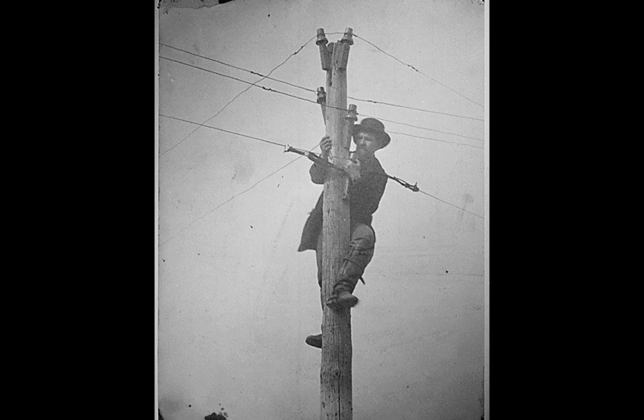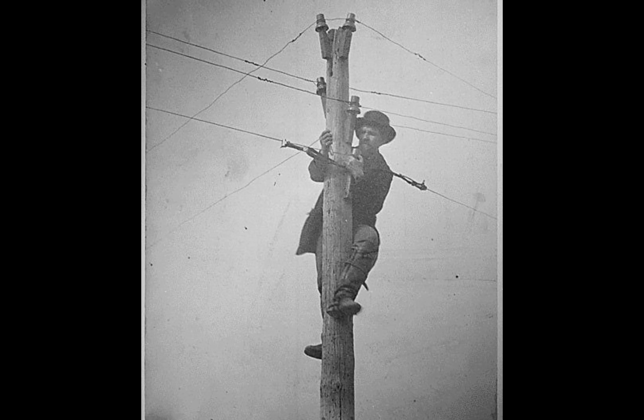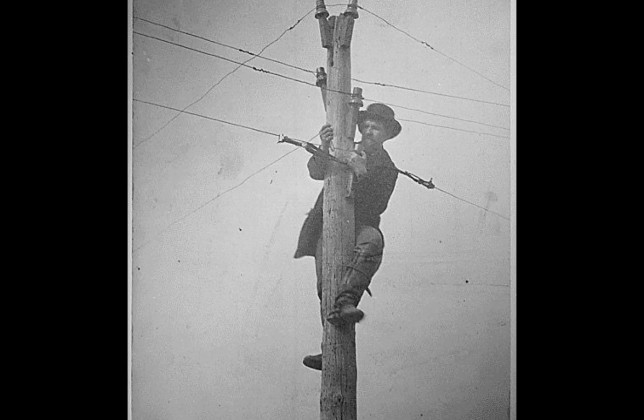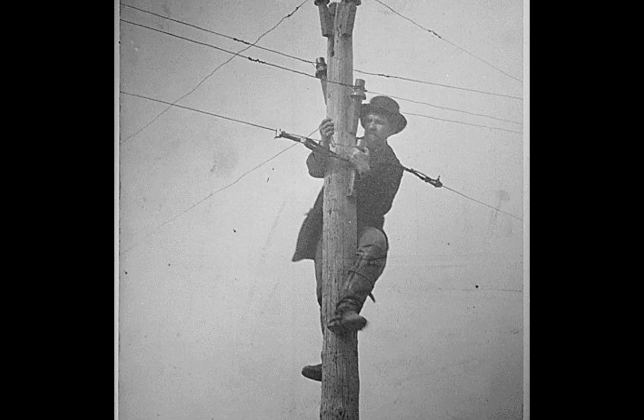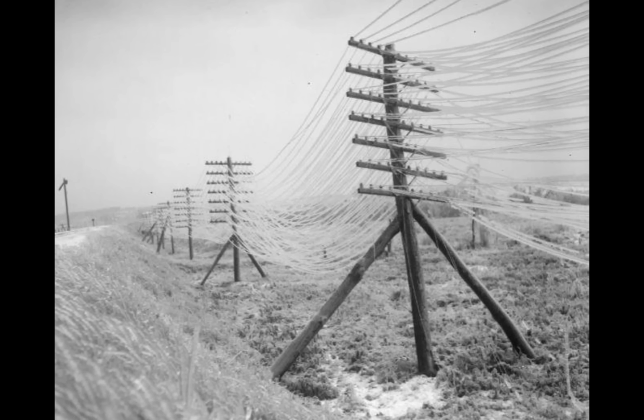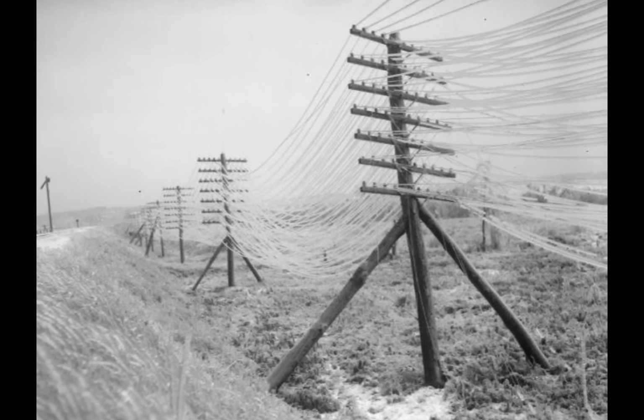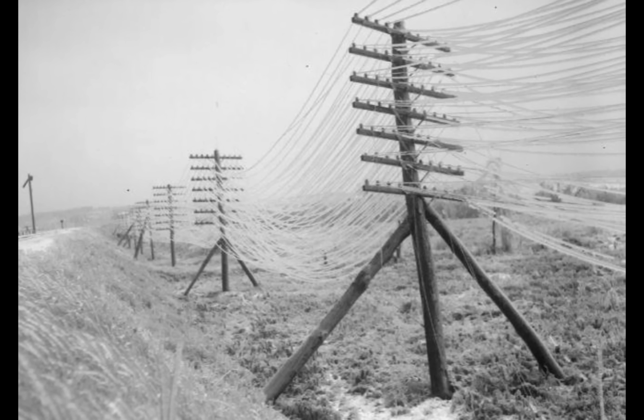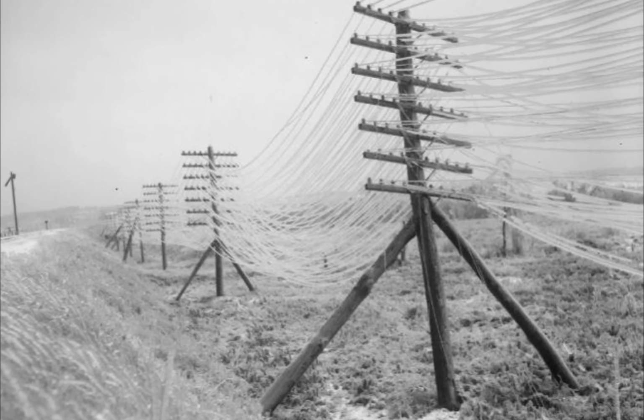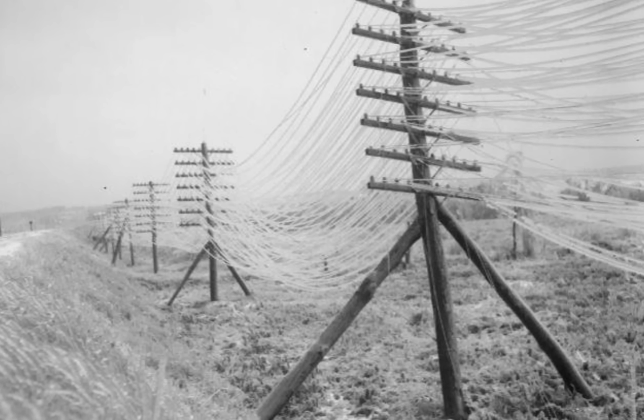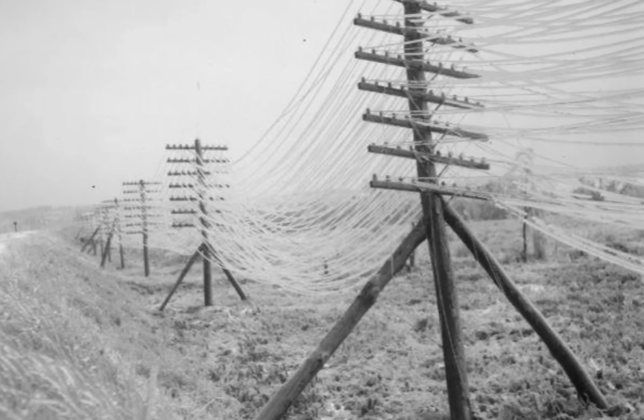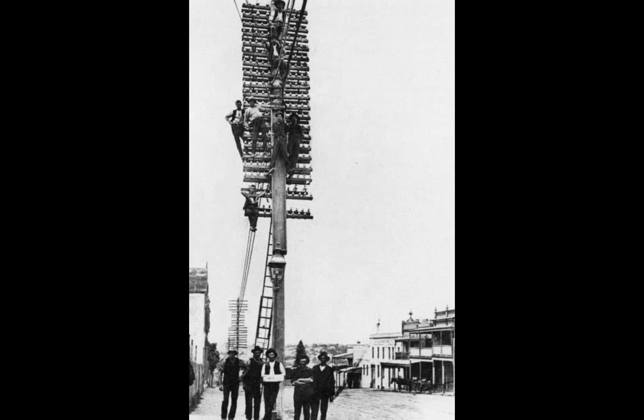Engineers tried compensating for the growing weight and leverage problem by strengthening the wooden crossarms and using heavier iron pins. This addressed the symptom, but not the cause. A bigger pin could hold a bigger insulator in place under static conditions, but it did nothing to solve the underlying issue. Any rigid, single-point mounting system concentrates all the mechanical stress from wind, ice, and wire tension onto one joint. Reinforcing the pin just meant the next failure point moved somewhere else in the assembly, usually the porcelain itself cracking near the base.